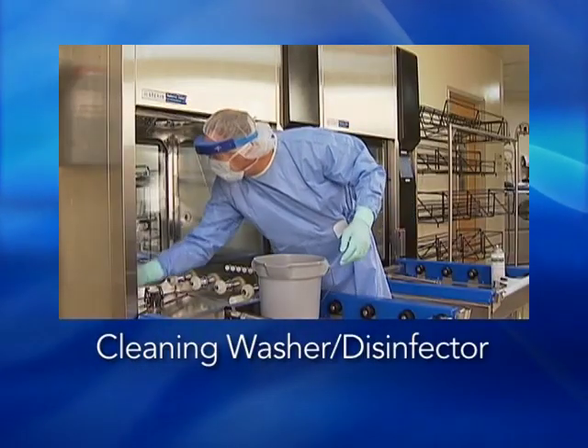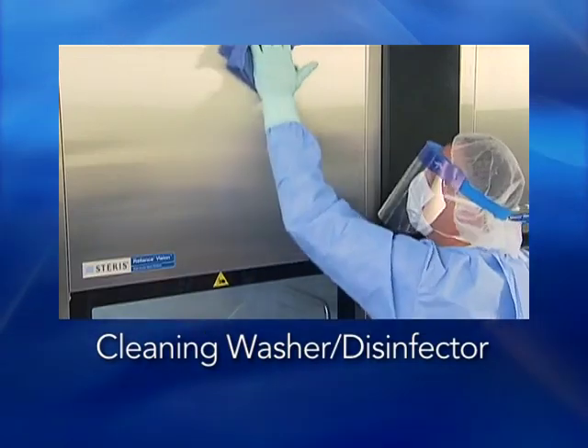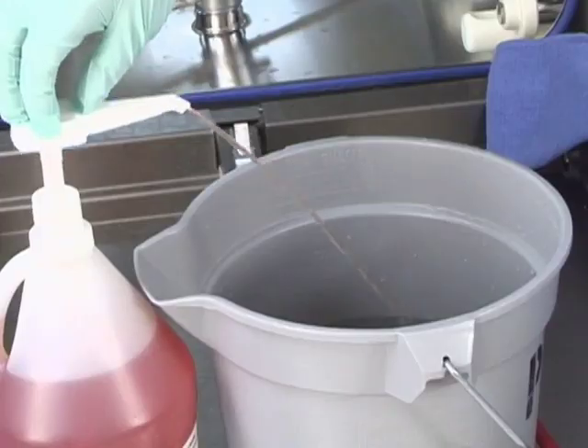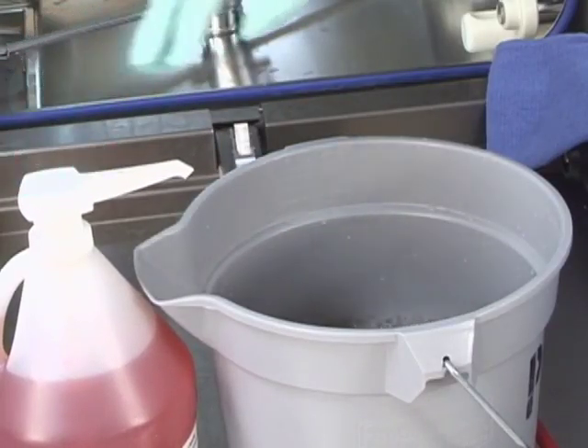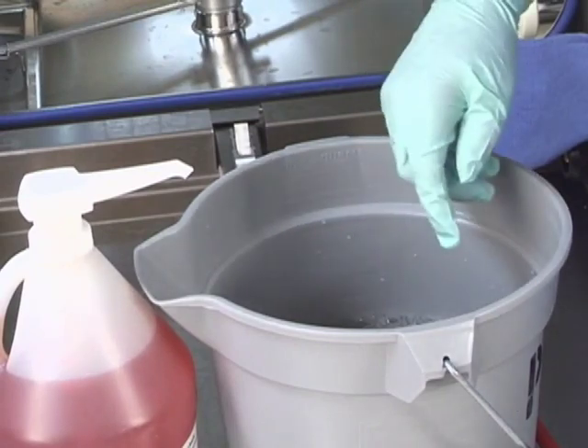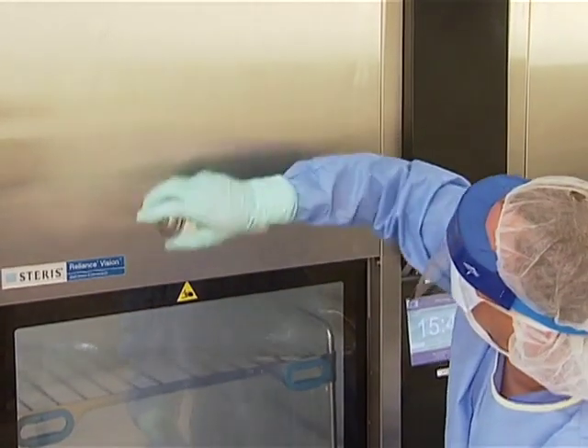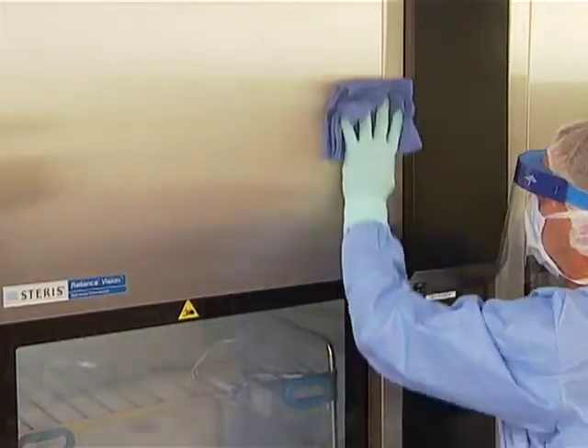You'll also need to clean the inside and outside of the washer disinfector once a week. For regular stains, use a general-purpose non-abrasive cleaner. For stubborn stains, use a stain remover and polish made for stainless steel surfaces. Apply the cleaning agent to a damp cloth or sponge.